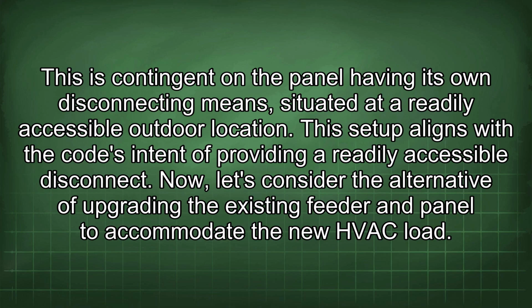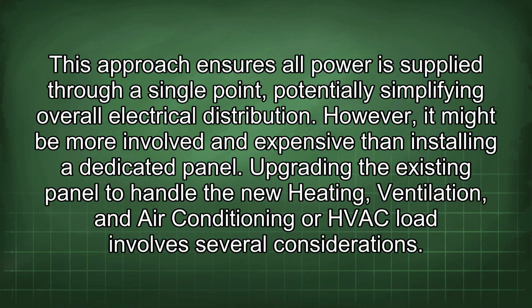Now, let's consider the alternative of upgrading the existing feeder and panel to accommodate the new HVAC load. This approach ensures all power is supplied through a single point, potentially simplifying overall electrical distribution. However, it might be more involved and expensive than installing a dedicated panel. Upgrading the existing panel to handle the new heating, ventilation, and air conditioning, or HVAC, load involves several considerations.